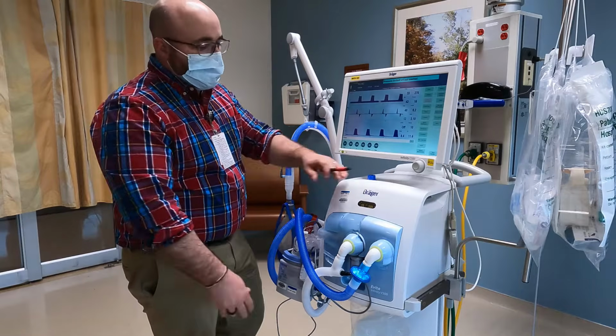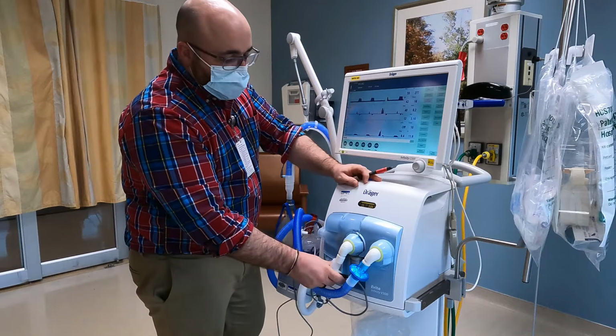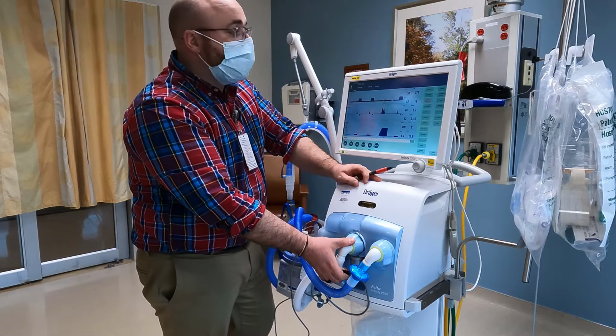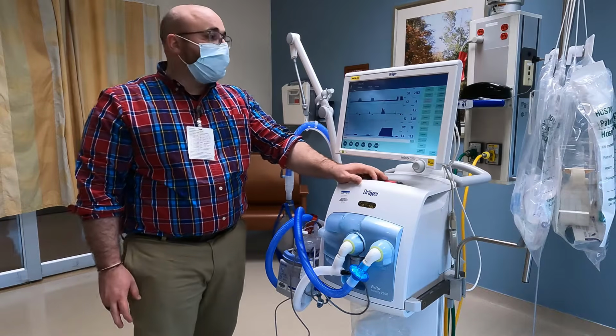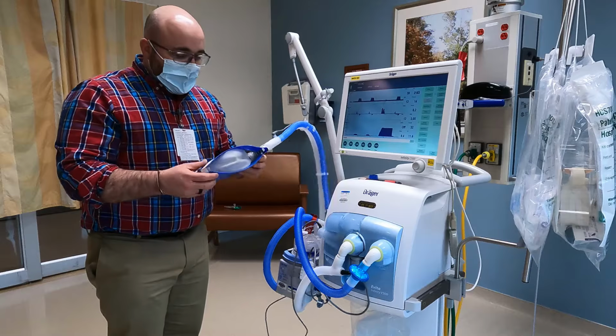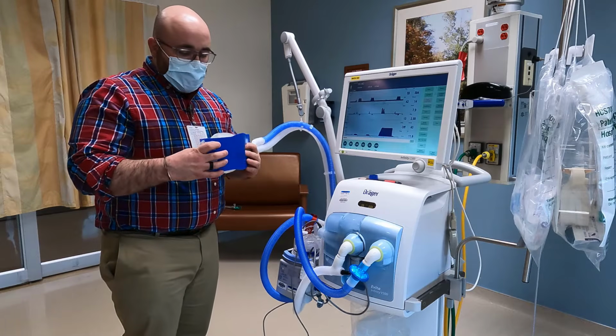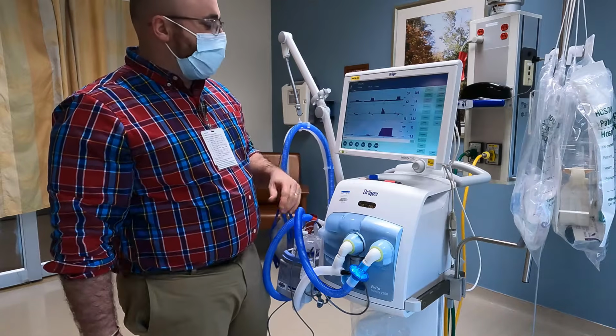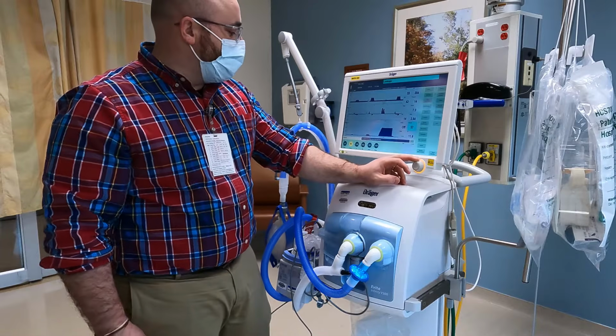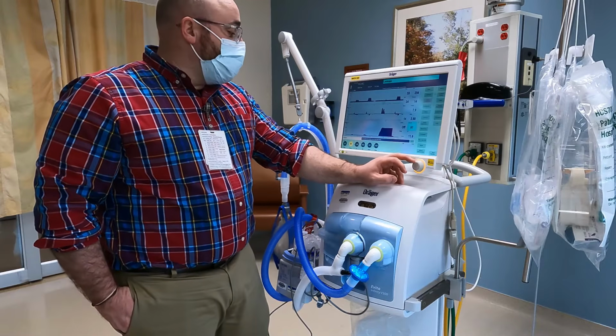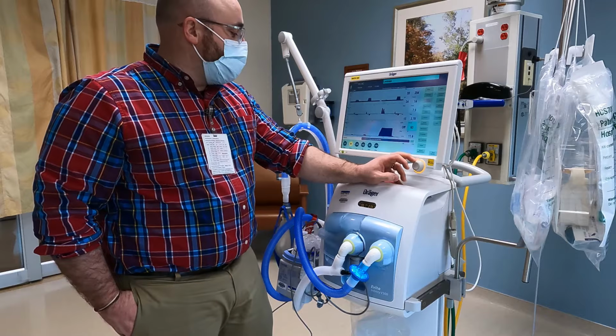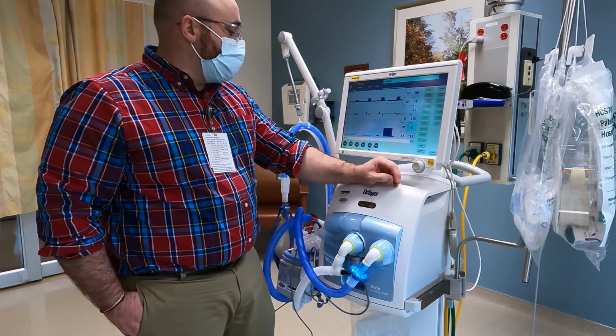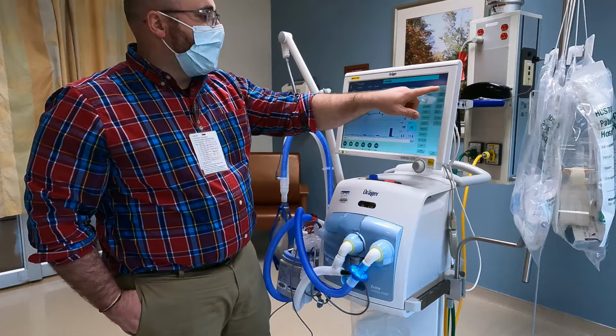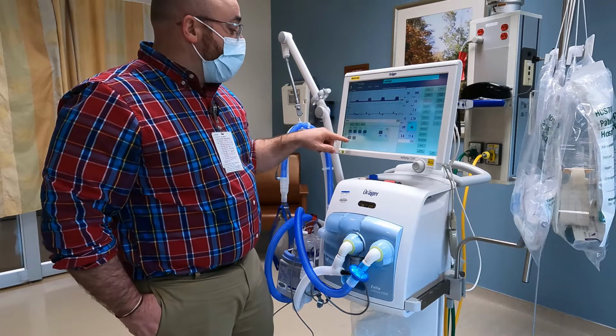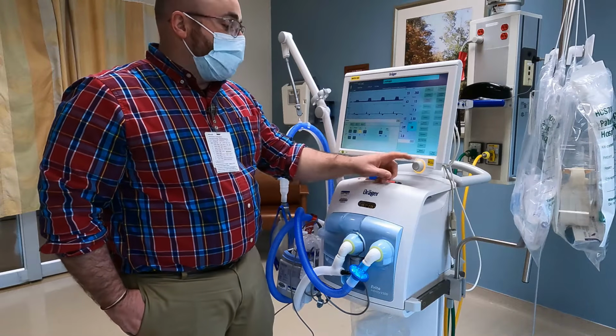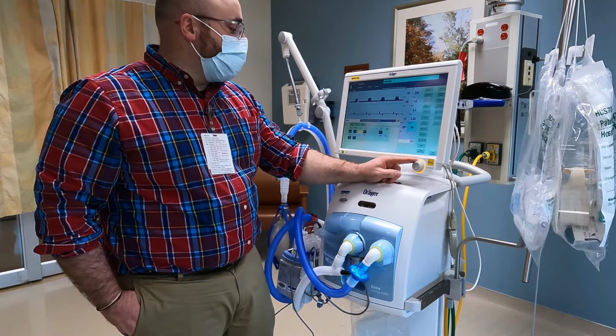Let's show a bigger alarm. More concern. So will that stay up there until that's fixed? Yes, it'll stay until it's fixed. Two ways to fix it: a more compliant patient, which I can't do much with this guy, or I could change the alarm. It's not something that intermittently pops up. Well, it could, like if I turn this volume down real low just because the test lung's being kind of a pain. It could pop up intermittently, but it should go away in a couple breaths, because it's gonna fix itself.